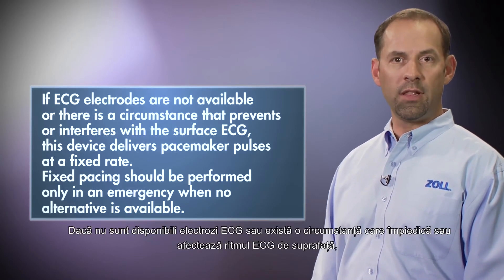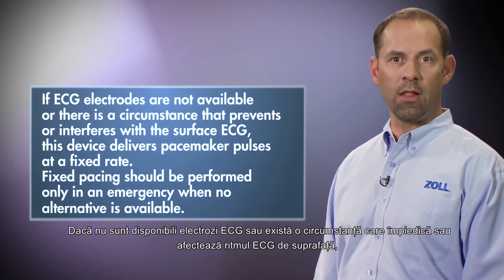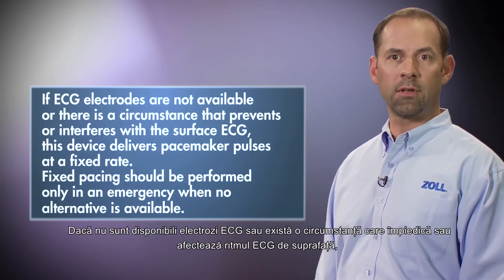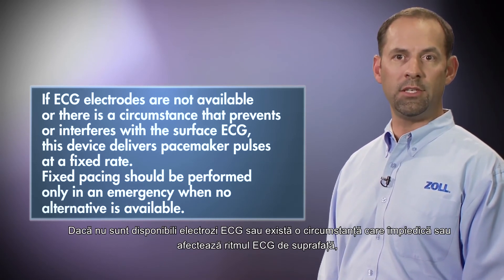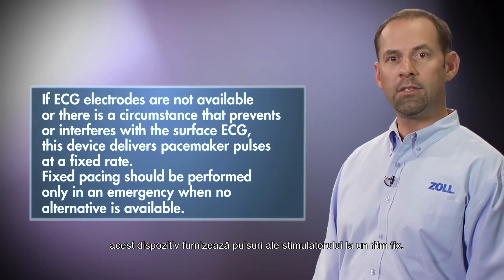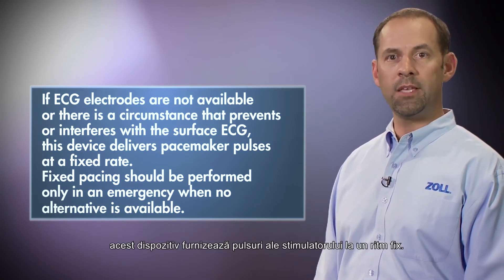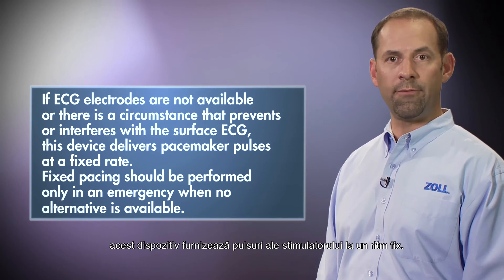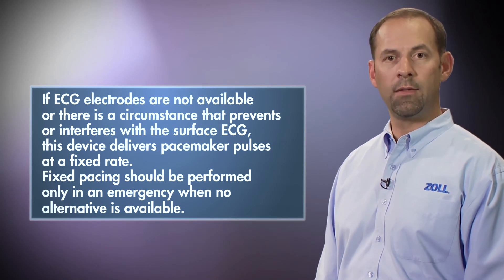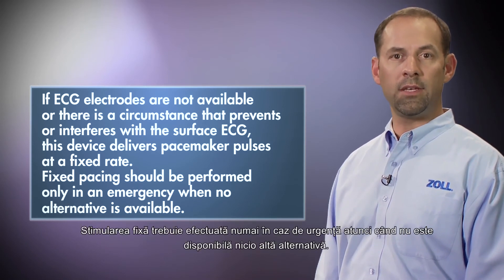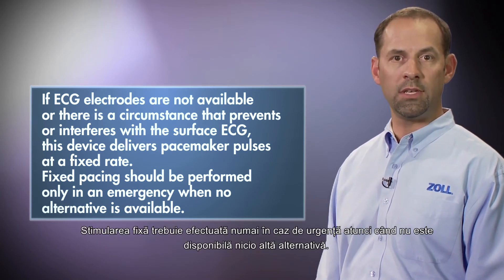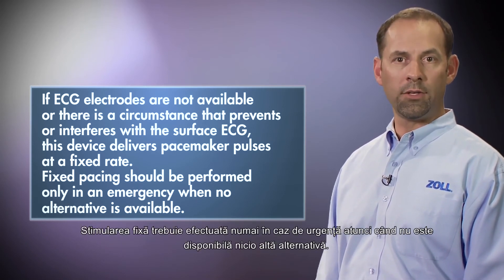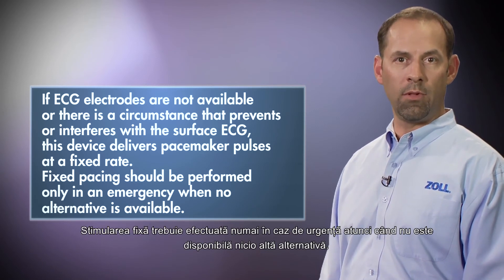If ECG electrodes are not available, or there is a circumstance that prevents or interferes with the surface ECG, this device delivers pacemaker pulses at a fixed rate. Fixed pacing should be performed only in an emergency when no alternative is available.